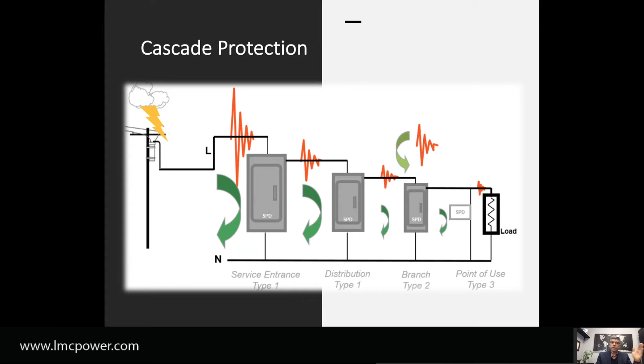Okay, so let's just understand this way now. If we have the utility at the entrance of the building, and we have a larger surge protection device, type 1 or category C, then in here we have the next two panels, distribution or branch. That's inside the building. Not every building just has one panel and then directly to the load. A lot of buildings have different distribution panels, and then it goes to sub panels or branch panels before it gets to the load, okay?